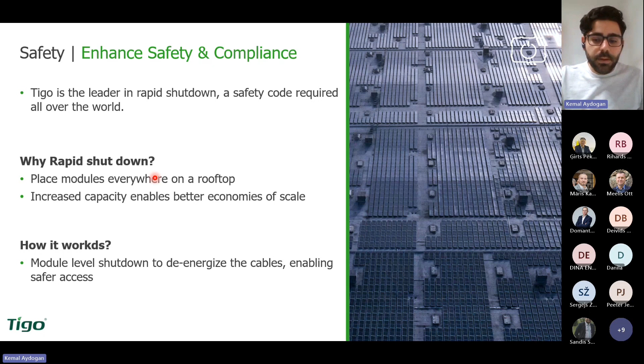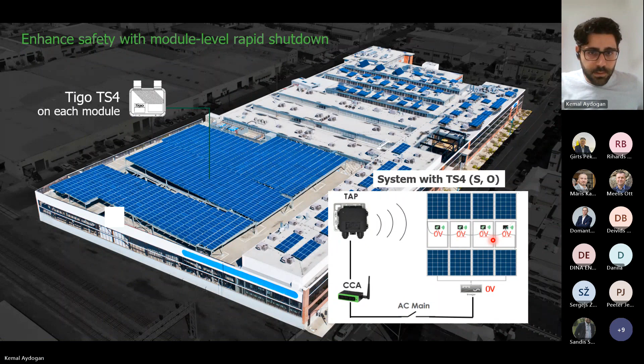Let's see it in the visualized mode. Each PV module has 30 volts, and in total you have 120 volts with 4 PV modules. Although you switch off your inverter, you still have this voltage. But with rapid shutdown solutions, since you are switching off at module level, you are going to have 0 volts on the total string and in between the strings. This is the reason why it enhances safety.